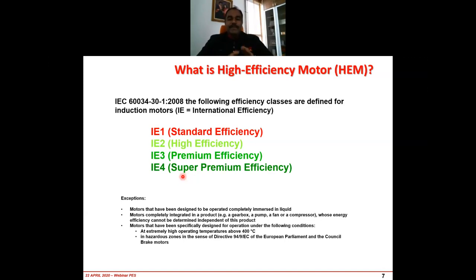For instance, if you buy a motor, and then you are connecting that to a pump system, the motor could be an IE4 motor, which is a super premium efficiency, meaning it gives you high efficiency. But if the IE4 motor is connected to a pump system which is probably a low efficiency pump system, obviously the motor system efficiency is not going to be super premium. So the entire system efficiency obviously should be lower. You cannot categorize it as IE4. So that's why when they categorize this IE1, IE2, IE3, IE4, it's only referring to the motor alone. So that's a point that we have to understand.